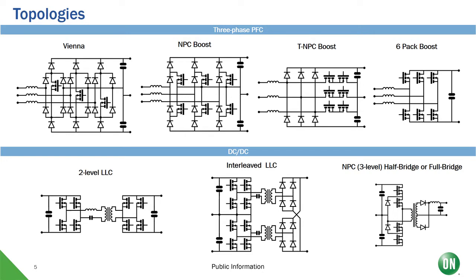If we look at typical PFC topologies, one of the most common is still the Vienna Rectifier. This is a simple and low-cost solution, so it's still very present in the market for lower-end solutions. However, as we want to improve efficiency, this option gets usually discarded, mainly because of unavoidably high conduction losses. Also, this topology is purely unidirectional, so now that part of the market moves to bidirectional topologies, this one gets automatically discarded as well.